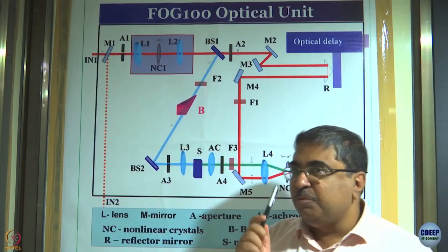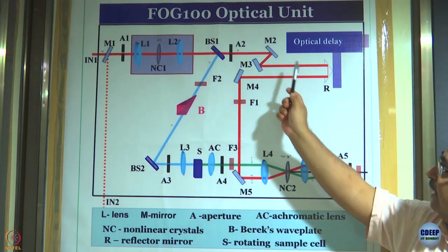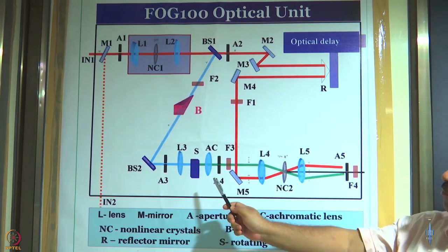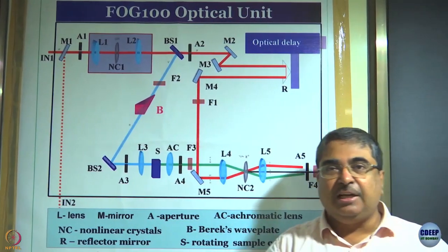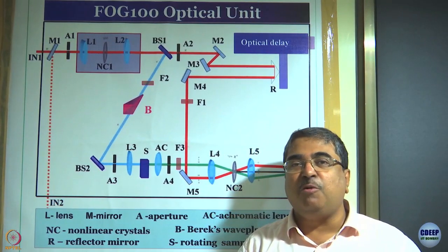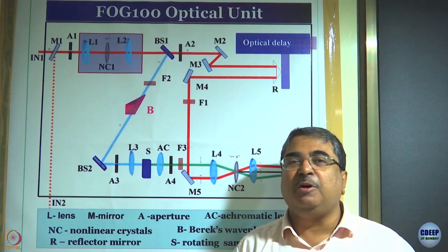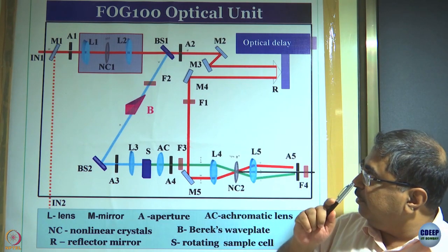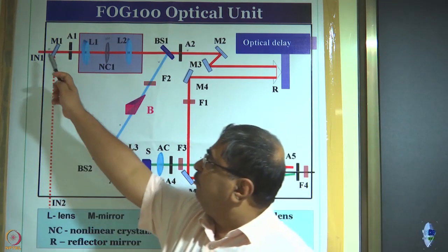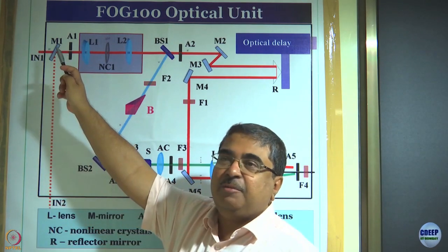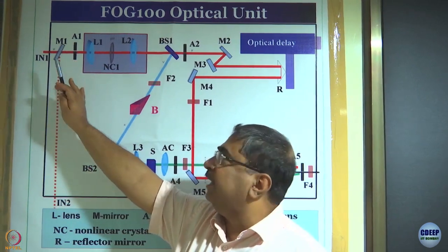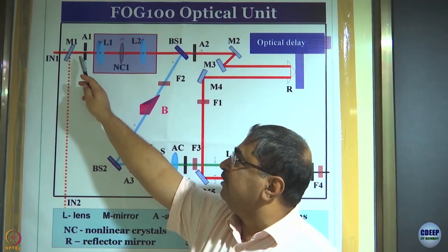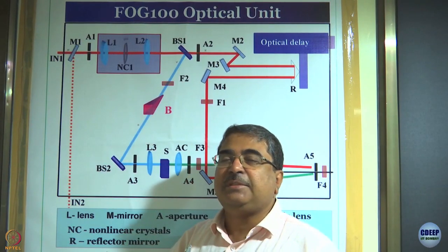I will first show you a diagram of the system, then we will go to the instrument. This is the layout of our optical unit for the FOG spectrometer. The spectrometer we use in our lab has the name FOG 100. It is from a company called CDP Corporation, which is based in Russia. We have red light, nominally 800 nanometers.